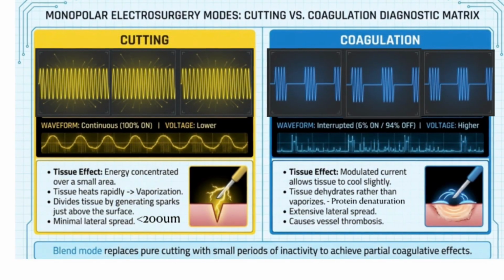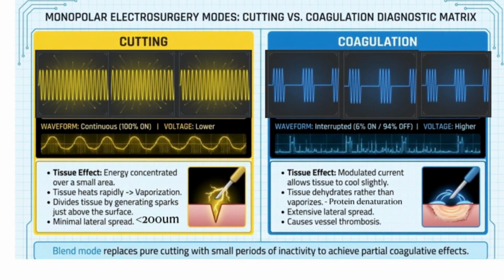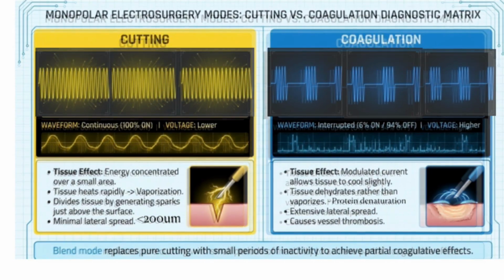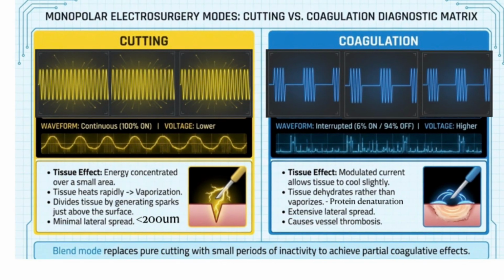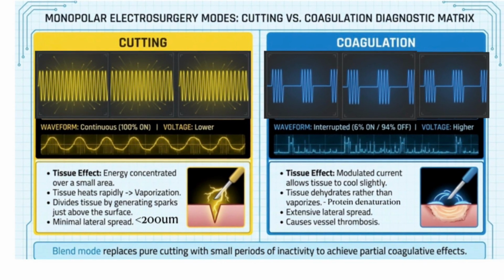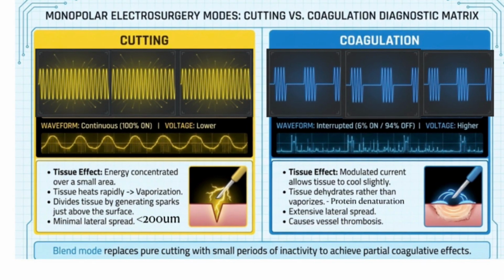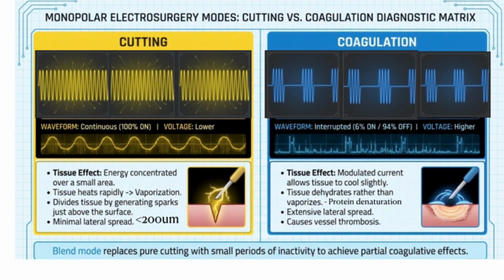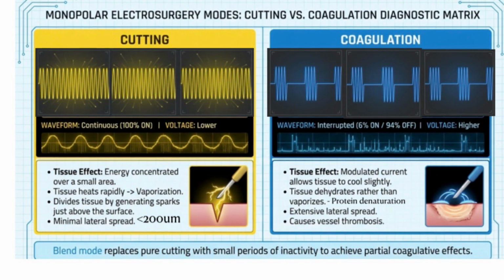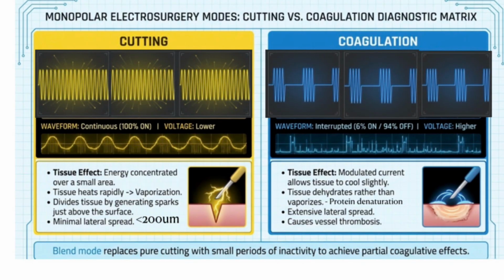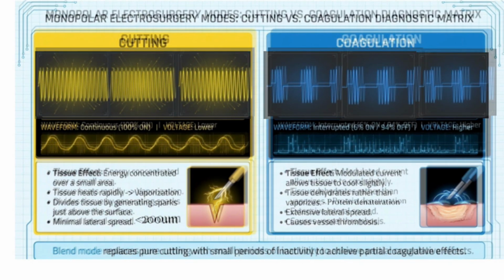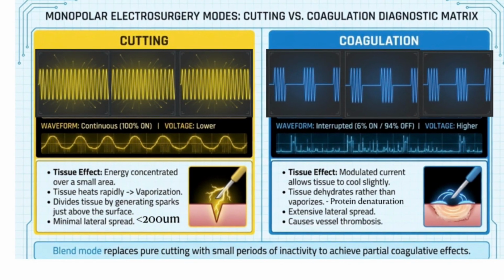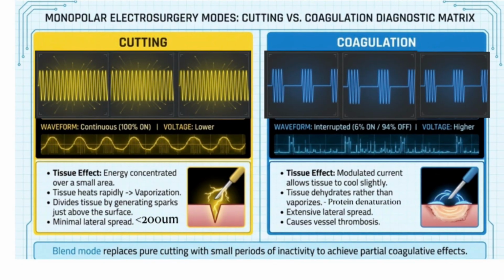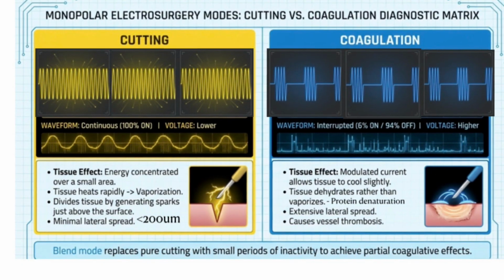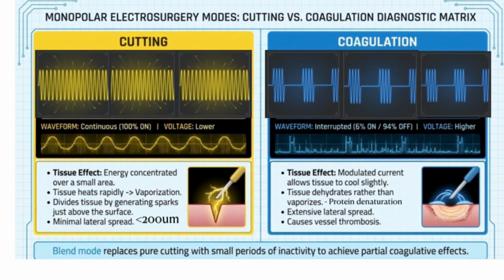The monopolar electrosurgery modes: the cutting versus the coagulation modes. In cutting, there is continuous passage of the current and the voltage is lower. The effect on the tissue: the energy is concentrated over a smaller area. Tissue heats rapidly, causing vaporization. This divides the tissue by generating sparks just above the surface. There is minimal lateral spread, less than 200 micrometers.